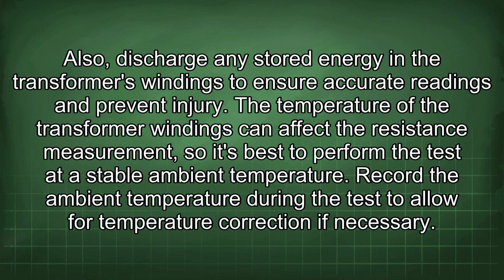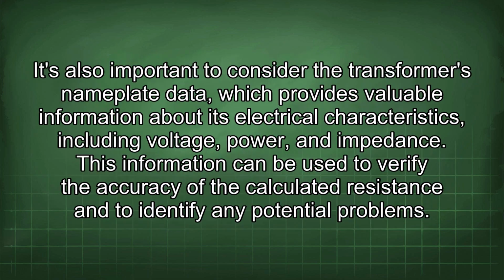The temperature of the transformer windings can affect the resistance measurement, so it's best to perform the test at a stable ambient temperature. Record the ambient temperature during the test to allow for temperature correction if necessary. It's also important to consider the transformer's nameplate data, which provides valuable information about its electrical characteristics, including voltage, power, and impedance.